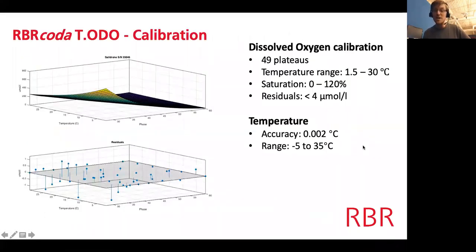So we calibrate all varieties of sensors in the same manner, where we first calibrate the thermistor on the sensor, as we do with all our marine thermistors across a range from -5 to 35 degrees Celsius, all to an accuracy of 0.002 degrees Celsius. We then calibrate the oxygen side of the sensor across 7 temperature ranges, ranging from 1.5 degrees Celsius to 30 degrees Celsius. And at each temperature point, we calibrate it at 7 different levels of oxygen saturation. This creates a 7x7 matrix of 49 points to fit our polynomial, our calibration model. And the residuals must be within 4 micromole for it to pass our calibration. Next slide, Eric.